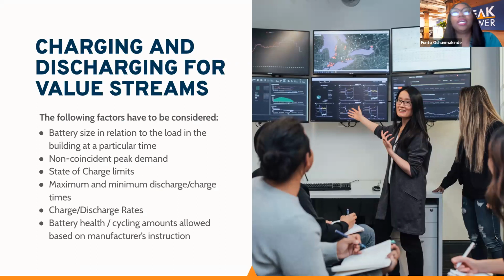So when charging and discharging the battery for the various value streams, there are some things to take into consideration, and some of the factors have been listed on the screen, so I will just talk about them. For example, one factor would be battery size in relation to the load. So you have some periods during the day for a commercial building, for example, towards the evening, where the load consumption is lower than the kilowatt hour capacity available on the battery. And for some buildings like that, you're not typically allowed to export to the grid, so it might not be allowed. So on such occasions, it's important to be mindful of the amount of kilowatt hour being discharged.